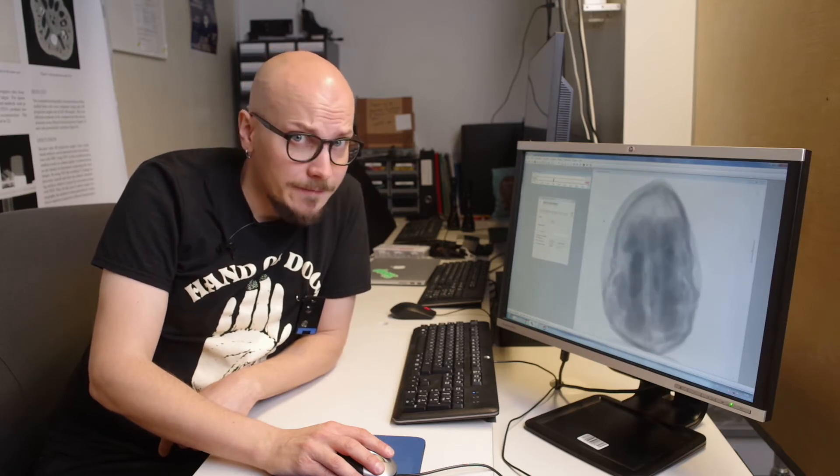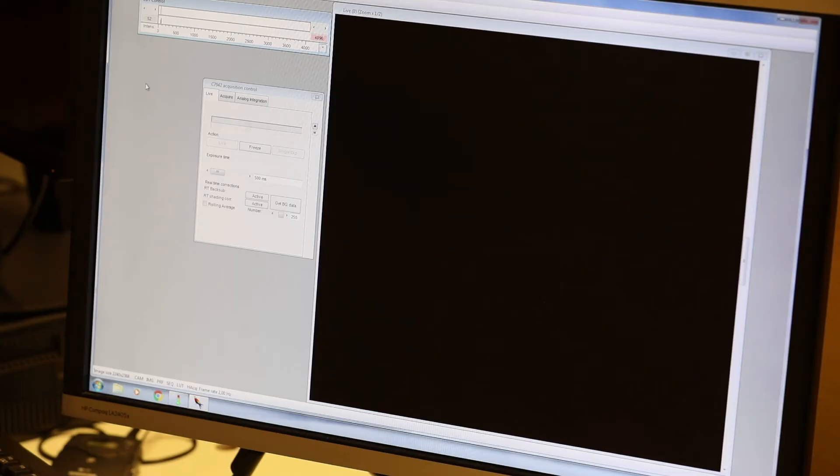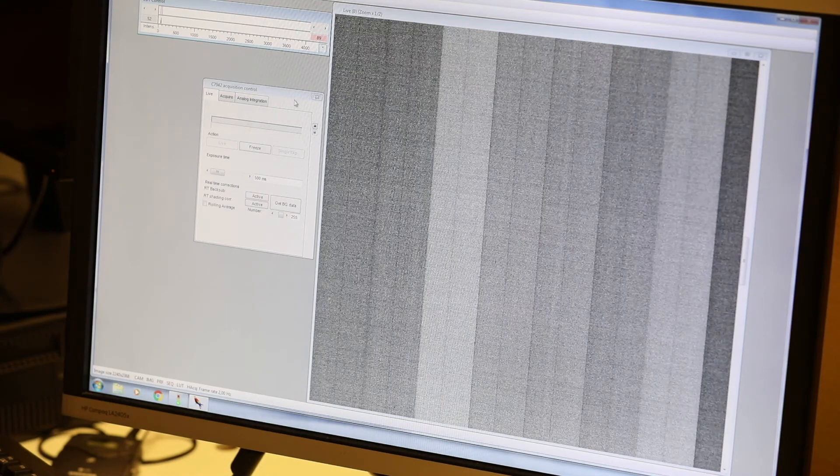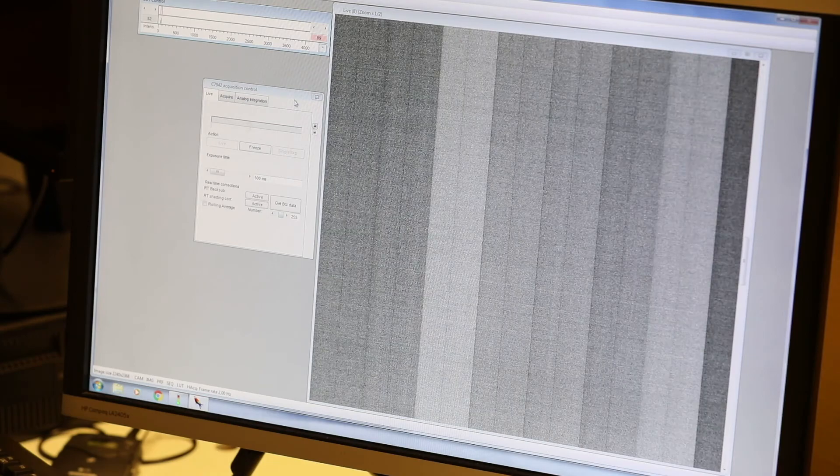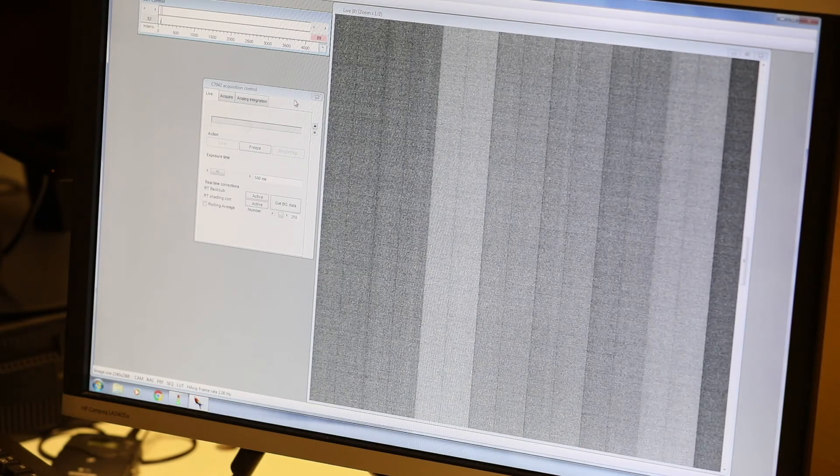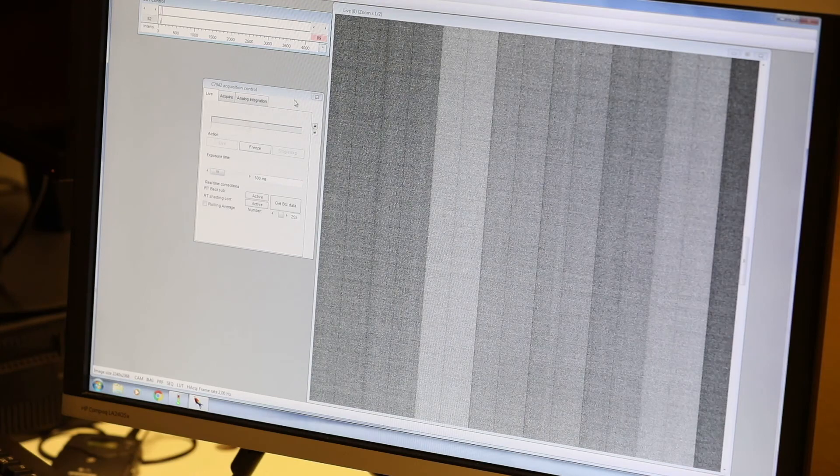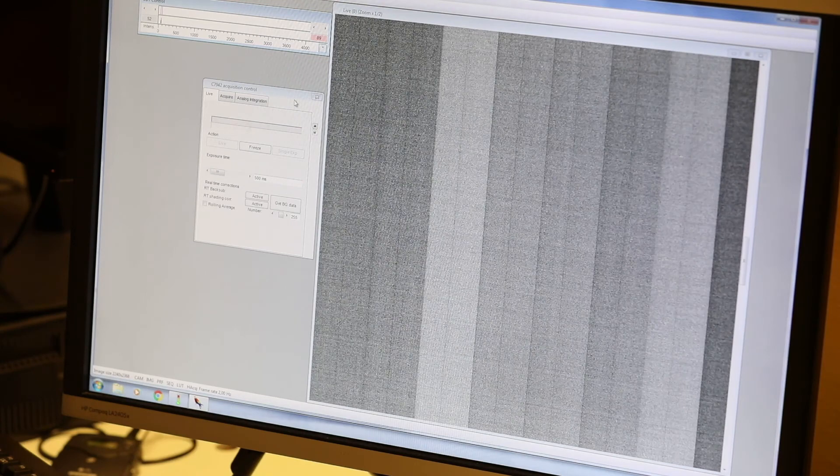One particularly important aspect of x-ray measurements is to calibrate the detector correctly. Here we see the signal from the detector when the x-ray source is off. Let's adjust the grayscale so that the smallest signal value is black and the highest is white. The image is not entirely black but consists of a set of fixed vertical bands and random electronic noise. This is called a dark current and it must be taken into account in the calibration of the x-ray data.